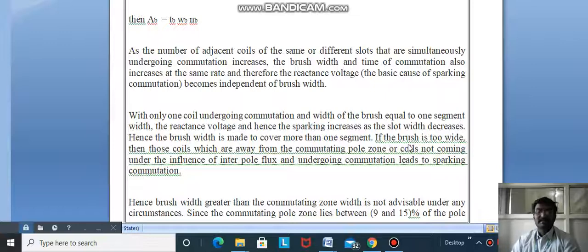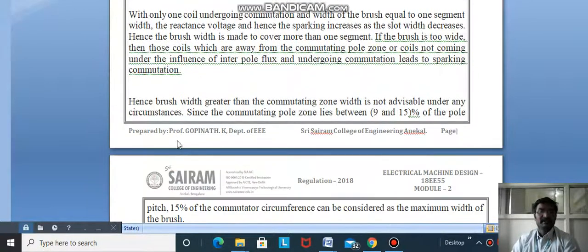If the brush is too wide, coils away from the interpole flux zone undergoing commutation lead to sparking. Hence brushes with greater width than the commutation zone are undesirable. Since the commutation zone lies between 9 and 15 percent of pole pitch.